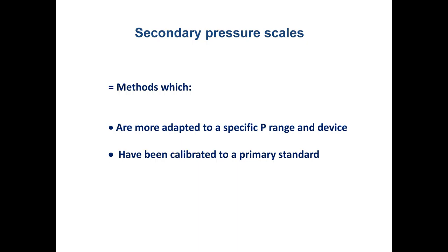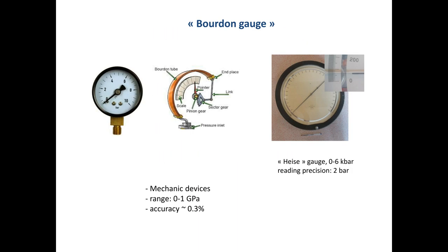All of the pressure gauges you will use in your future career are secondary pressure gauges. The simplest one — you know it from home probably — is the famous Bourdon gauge. When you go into the lab, it's often the first thing you see. Inside there is a tube in the form of a hemicircle, and it's hollow. You inject pressure inside and it deforms. This deformation is picked up by a mechanical mechanism and transferred to a pointer, which gives you the pressure once calibrated.